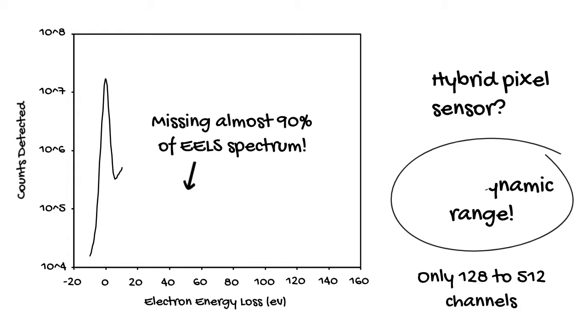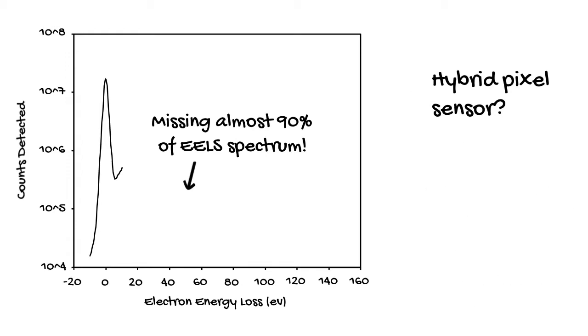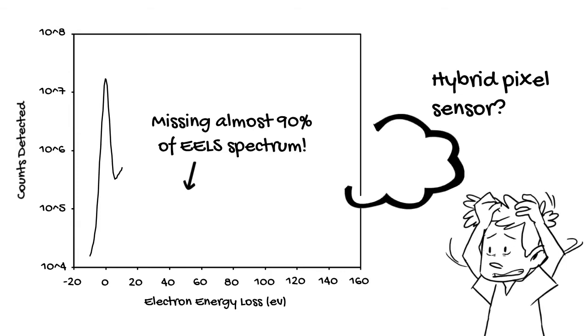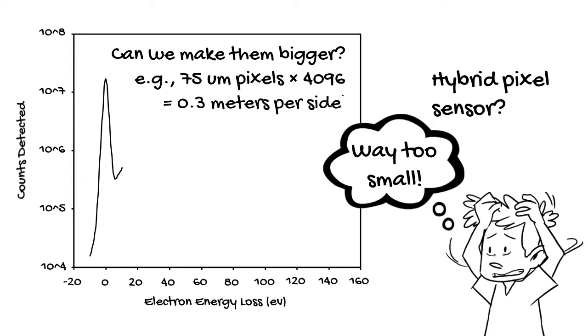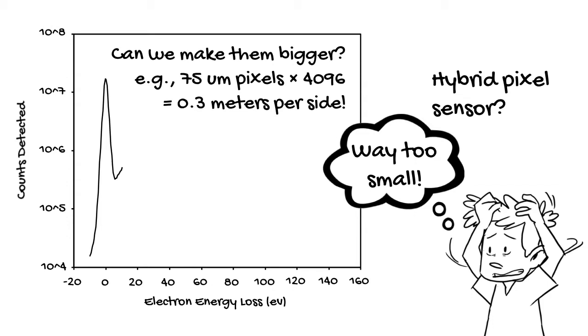In fact, with so few channels, the dynamic range isn't even necessary, because you simply don't have enough channels to capture a spectrum wide enough to cover a large intensity range. Although there are a few recent hybrid pixel detectors that are larger, it remains infeasible to manufacture a hybrid detector with 4K channels, let alone actually fitting something that large on the end of a spectrometer. So while there are good applications for hybrid pixel detectors, EELS is clearly not one of them. These detectors are simply too small to be useful.